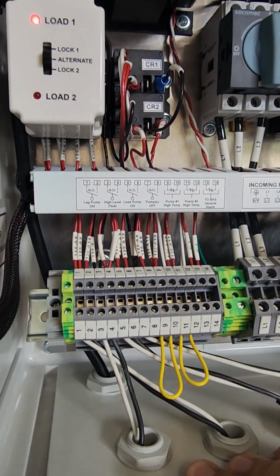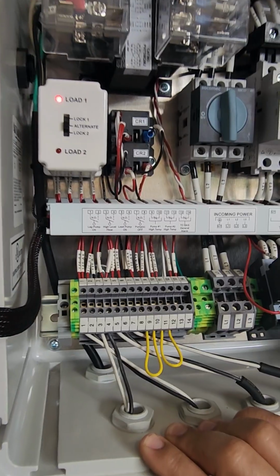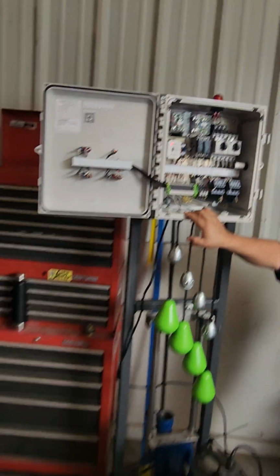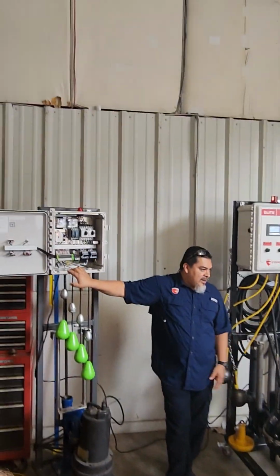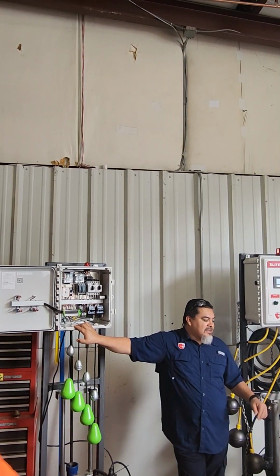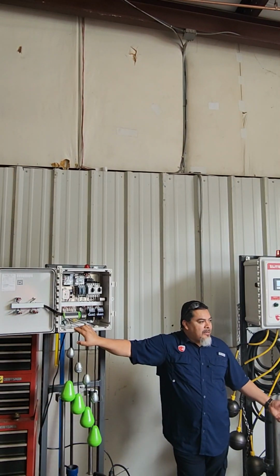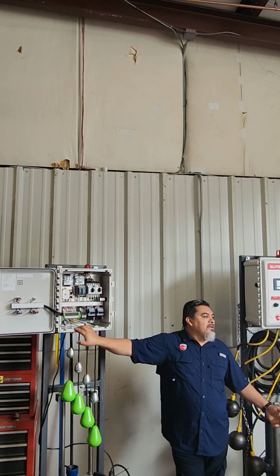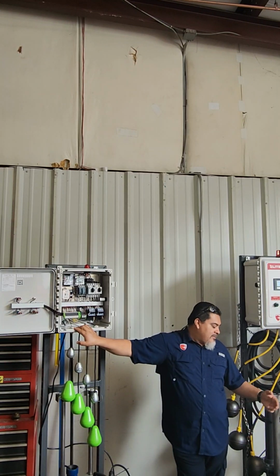So yes, if your pumps don't come on because you don't hear the clicking on the contactor, that's indicating your high temps are not on there. They probably don't work with the pump and you can bypass it. It'll still activate the pump, but of course you lose the safety feature. Just to get them running, yeah, to get them running, getting the pump down.